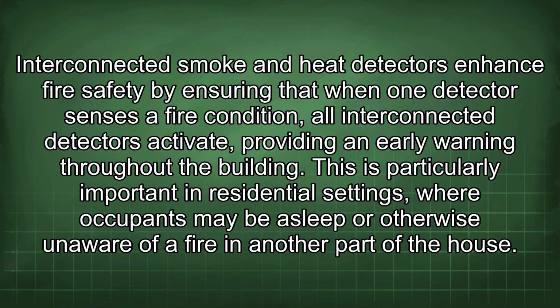Interconnected smoke and heat detectors enhance fire safety by ensuring that when one detector senses a fire condition, all interconnected detectors activate, providing an early warning throughout the building. This is particularly important in residential settings where occupants may be asleep or otherwise unaware of a fire in another part of the house.